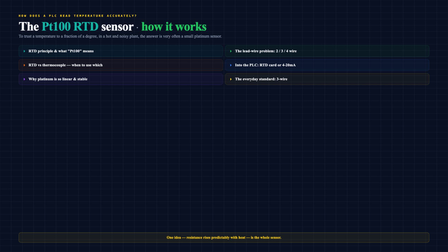In this video, I will explain what an RTD is and what the name Pt100 actually means. Then the lead wire problem, and why you see 2-wire, 3-wire, and 4-wire versions. How it compares to a thermocouple, and how it finally reaches your PLC. Let us start with the principle.